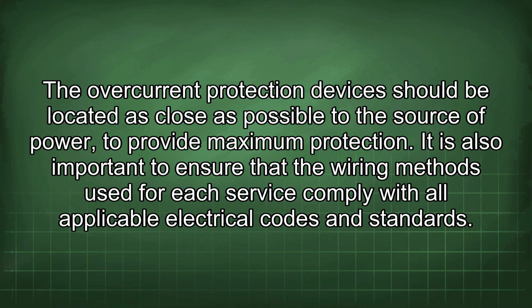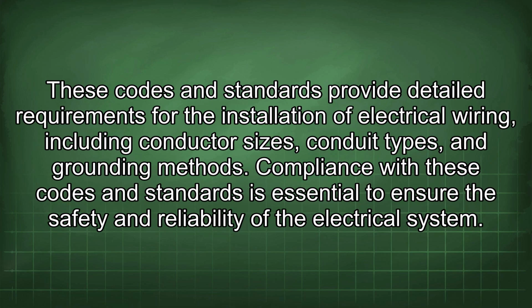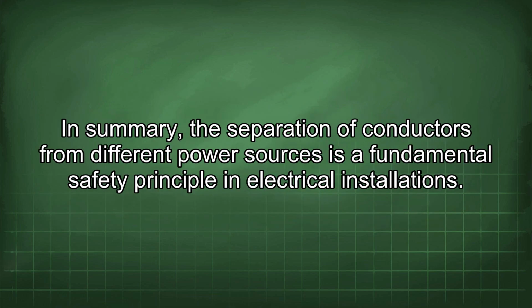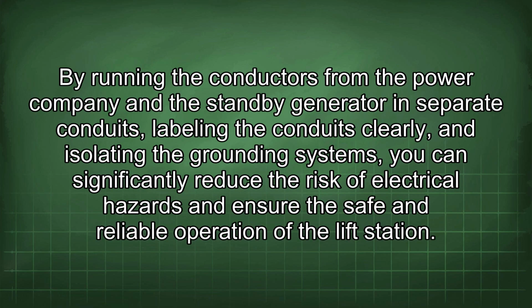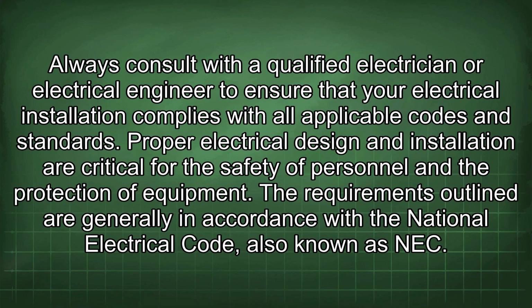It is also important to ensure that the wiring methods used for each service comply with all applicable electrical codes and standards. These codes and standards provide detailed requirements for the installation of electrical wiring, including conductor sizes, conduit types, and grounding methods. Compliance with these codes and standards is essential to ensure the safety and reliability of the electrical system. In summary, the separation of conductors from different power sources is a fundamental safety principle in electrical installations. By running the conductors from the power company and the standby generator in separate conduits, labeling the conduits clearly, and isolating the grounding systems, you can significantly reduce the risk of electrical hazards and ensure the safe and reliable operation of the lift station. Always consult with a qualified electrician or electrical engineer to ensure that your electrical installation complies with all applicable codes and standards.